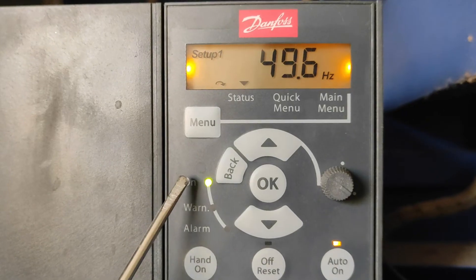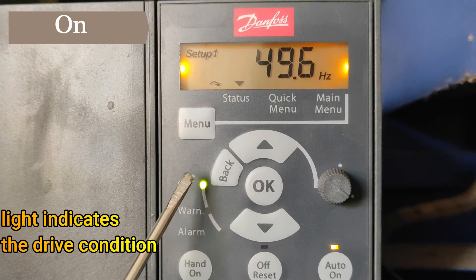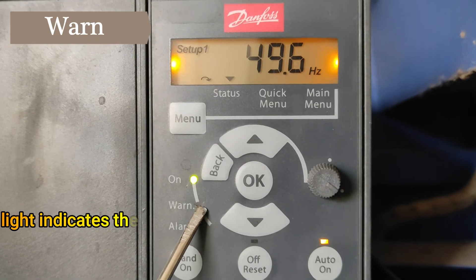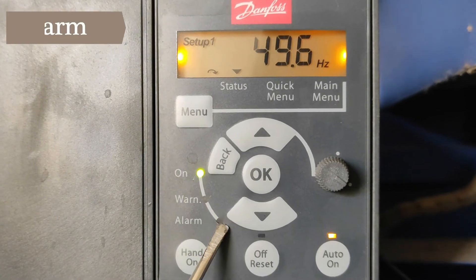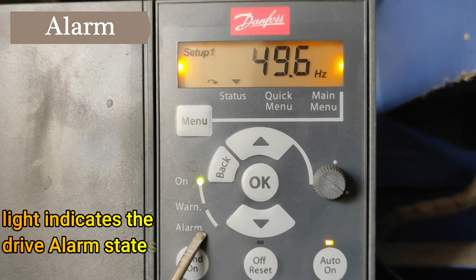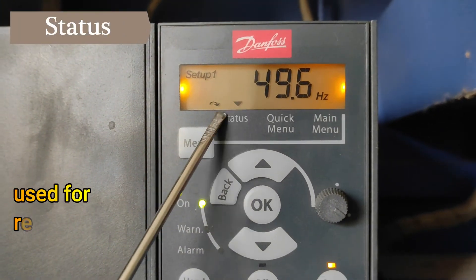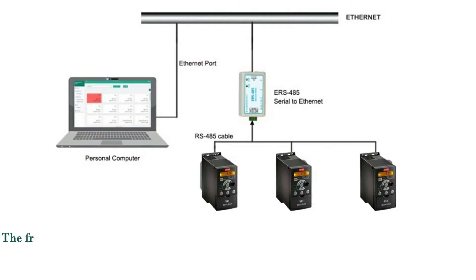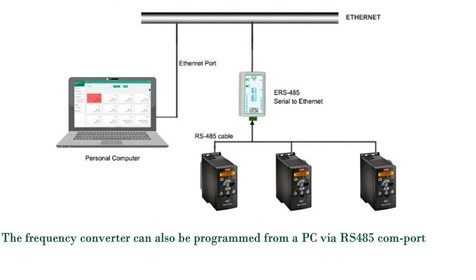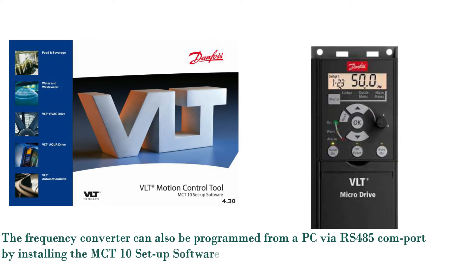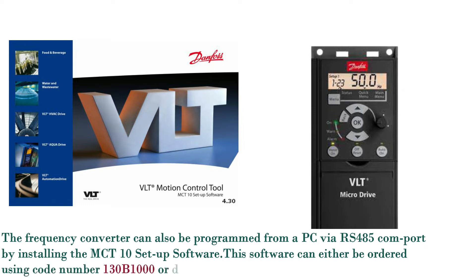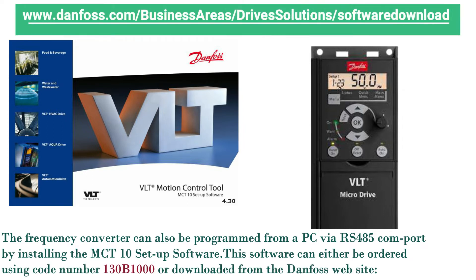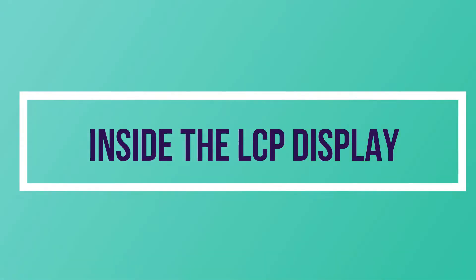Indicator lights: On indicator light indicates drive condition; Warn indicator light indicates drive warning states; Alarm indicator light indicates drive alarm states. Status is used for readouts only. Quick menu is used for access to quick menus 1 and 2. The frequency converter can also be programmed from a PC via RS-485 COM port by installing MCT-10 setup software, which can be ordered using code number 130B1000 or downloaded from the Danfoss website.